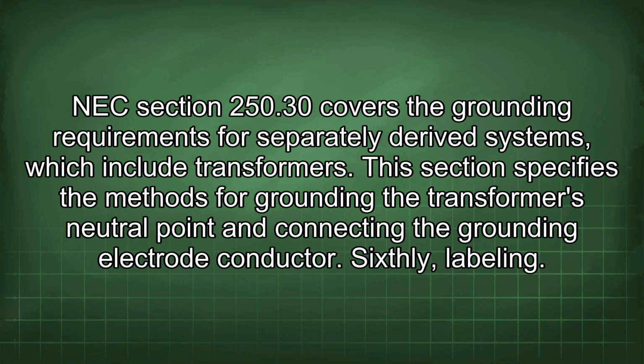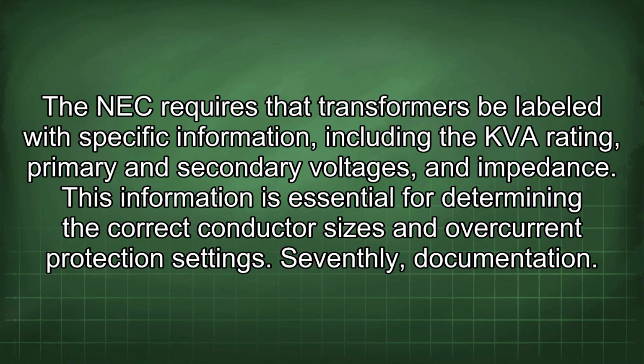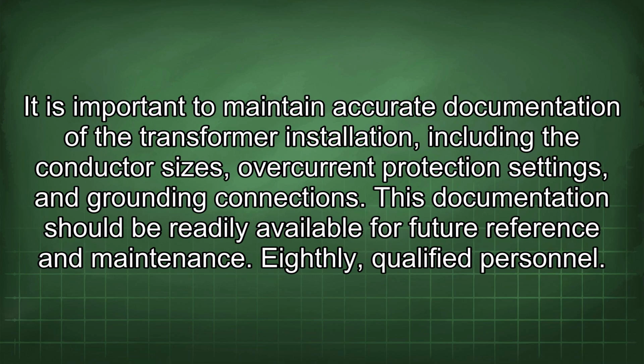Sixthly, labeling. The NEC requires that transformers be labeled with specific information, including the kVA rating, primary and secondary voltages, and impedance. This information is essential for determining the correct conductor sizes and overcurrent protection settings. Seventhly, documentation. It is important to maintain accurate documentation of the transformer installation, including the conductor sizes, overcurrent protection settings, and grounding connections. This documentation should be readily available for future reference and maintenance.